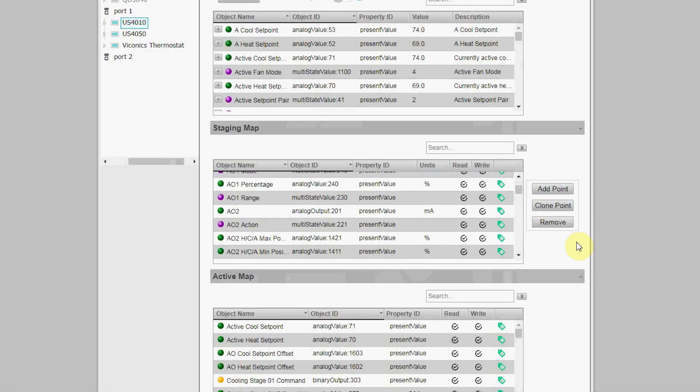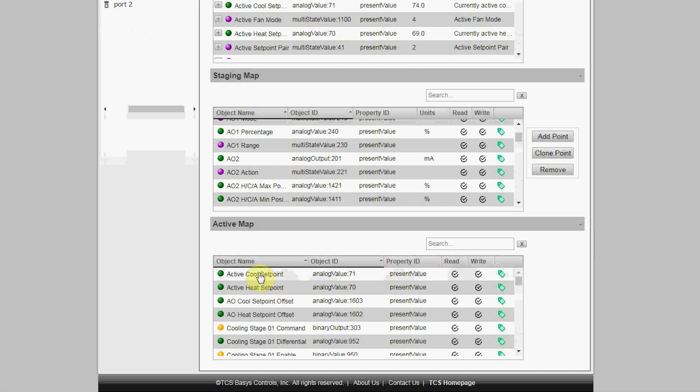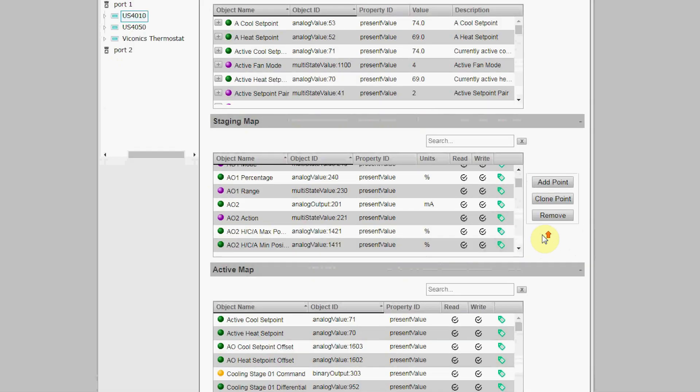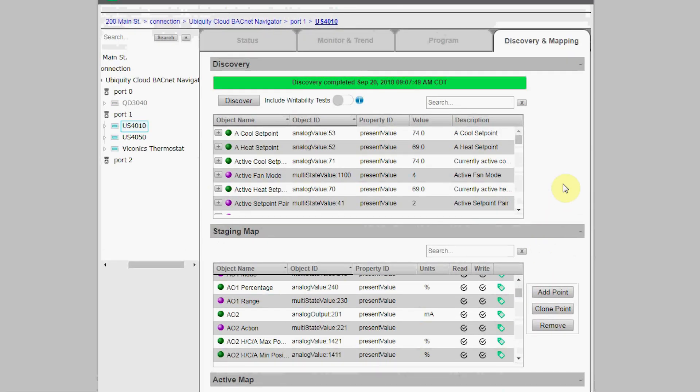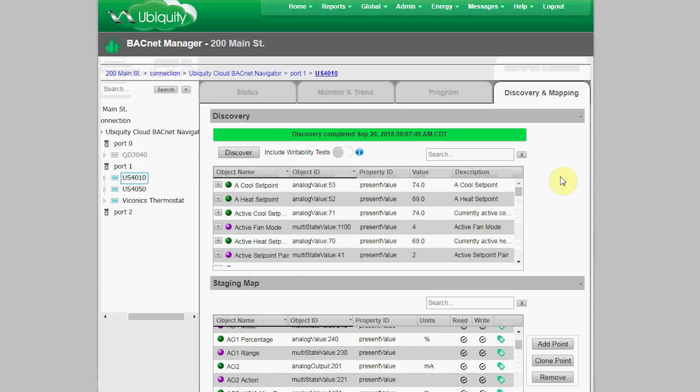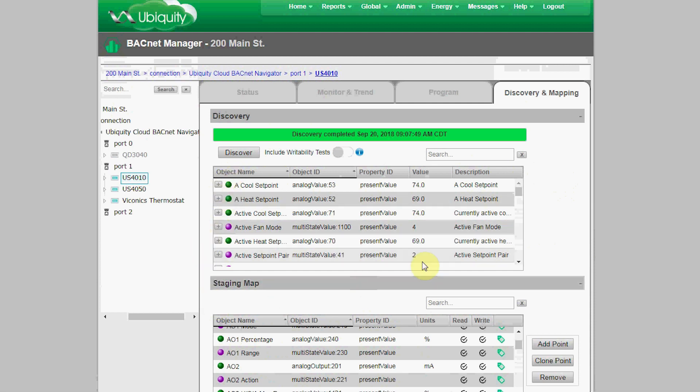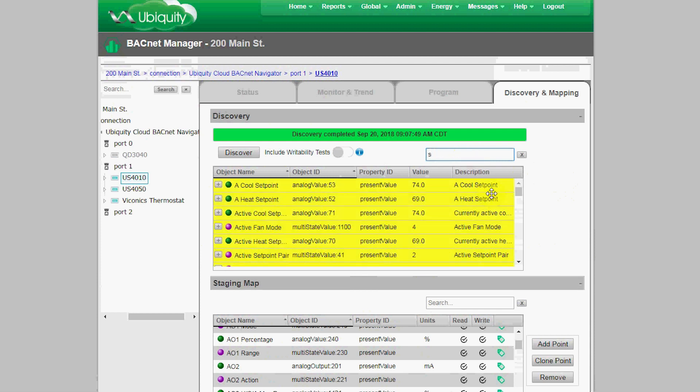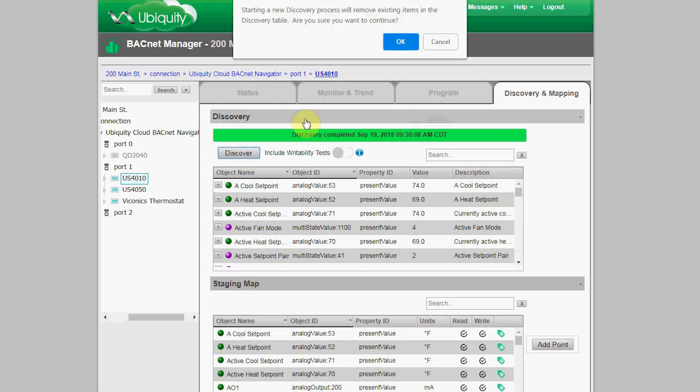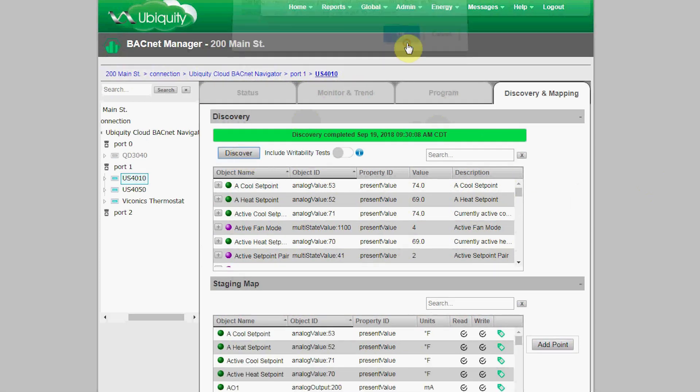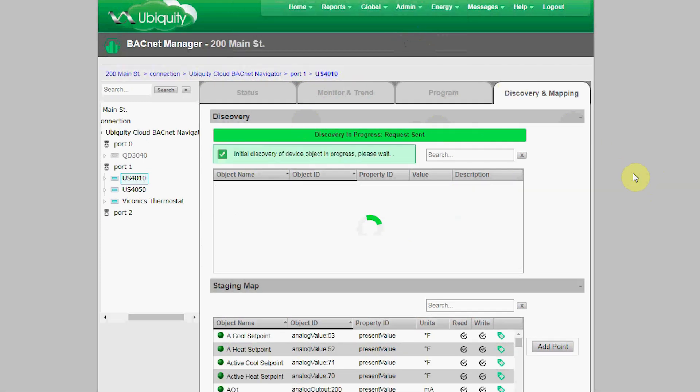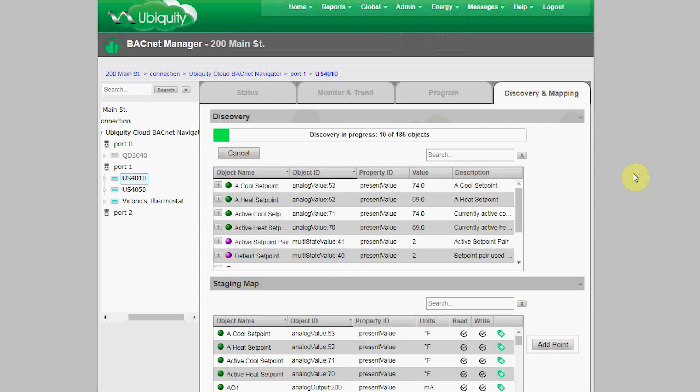That tagging is used to set up a point to be read, written, monitored, trended, or available for programming. The Active Map is where points that have been staged have been dragged and dropped so you can actively program, monitor, and trend in Ubiquity. This US 4010 device has already been set up, but we'll use this for demonstration purposes. You'll also notice that each of these three sections has its own search field.